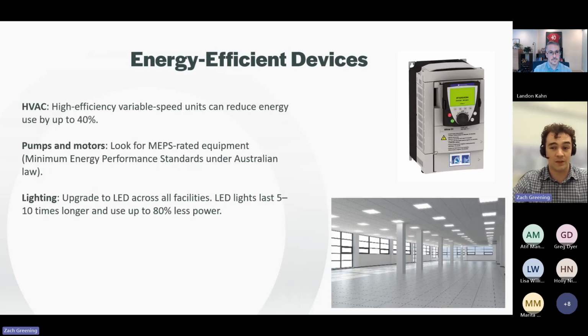HVAC typically accounts for 40 to 60% of energy use in commercial office buildings in Australia, especially in larger or older assets. The most impactful upgrade you can make is switching to high efficiency variable speed units or variable speed drives, VSDs. What is a VSD? Basically, instead of something operating at 100% capacity when it's turned on and 0% capacity when it's turned off, VSDs can ramp up and down based on real-time temperature and load requirements to help avoid energy spikes and reduce wear and tear while maintaining occupant comfort more efficiently.